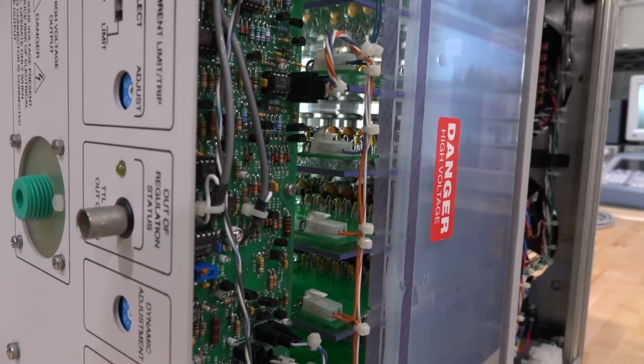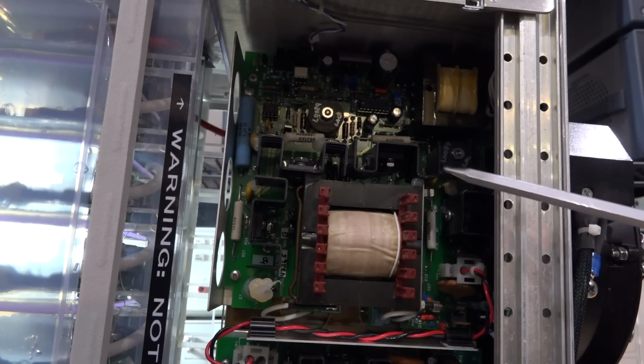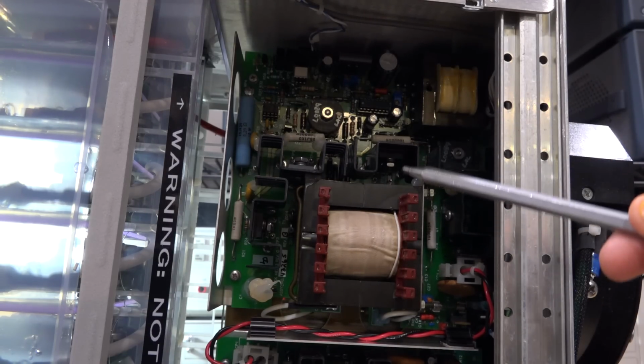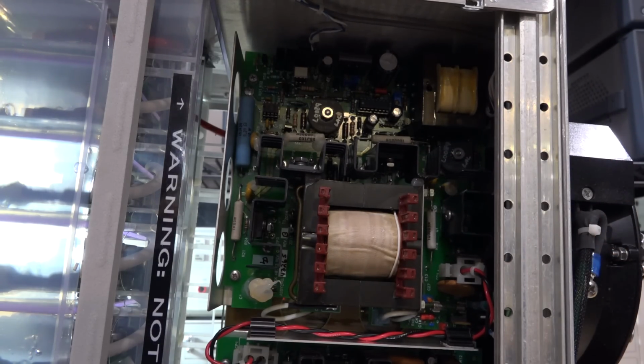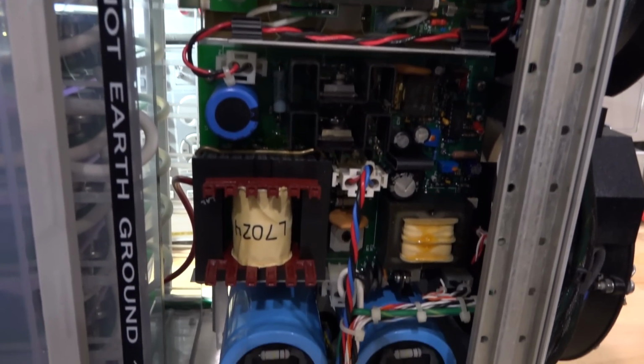But yeah, let's take a look at the high voltage side. And here are the two fixed high voltage power supplies. So these are probably the least interesting part of this entire instrument, because they're just simply a transformer, just like the other instruments we saw, to produce and rectify and create a single output. Now this is still at 20,000 volts, so that is certainly different than what we were seeing before in terms of being only at 5,000 volts, but really they're doing the same thing. And there's two of them.